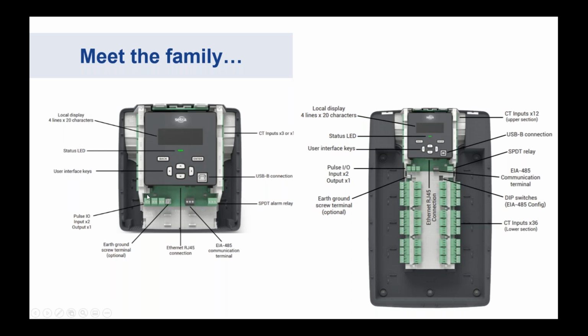So we'll have 2 pulse inputs and 1 pulse output. The inputs you can tie to a water meter, a gas meter, and accumulate those values and get those up to your whatever preferred protocol, be it Modbus or BACnet. You also have user interface keys, a status LED that will indicate locally alarms, as well as a 4-line display that'll be backlit so you can navigate some of the high-level information data right there at the meter without having to log in.